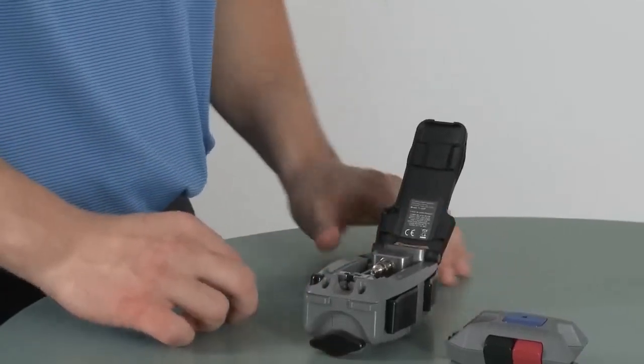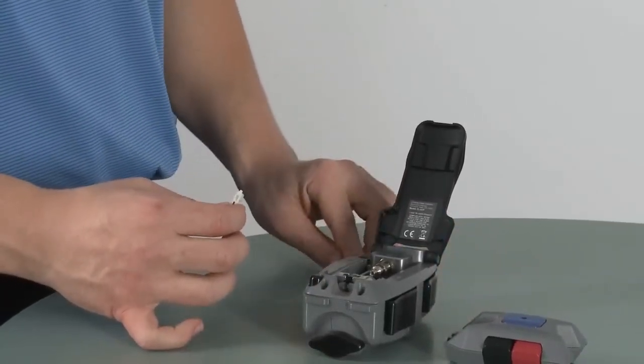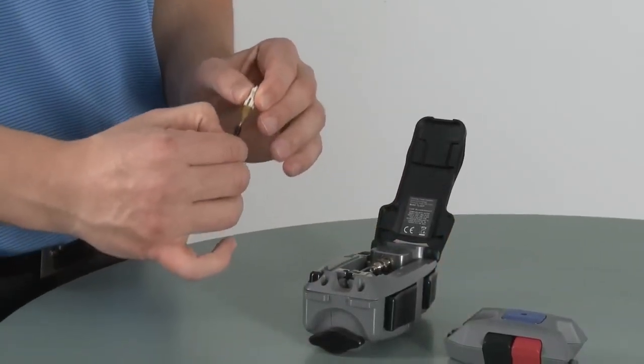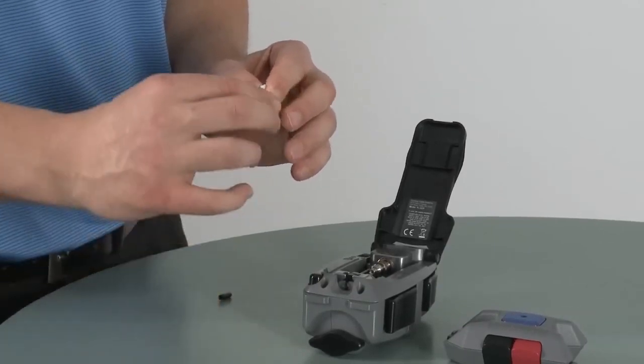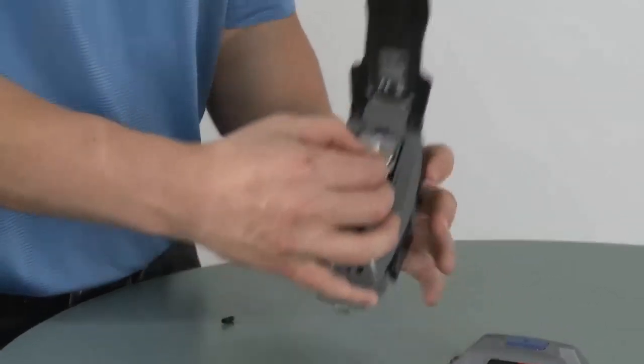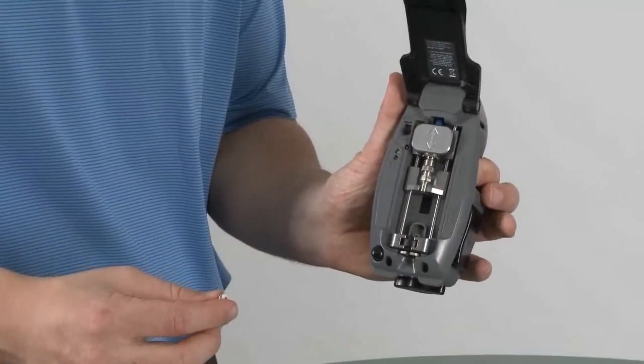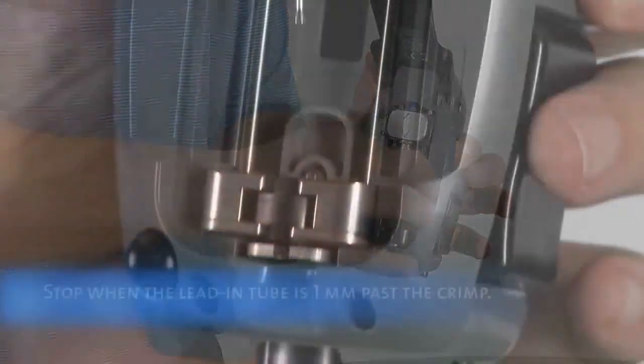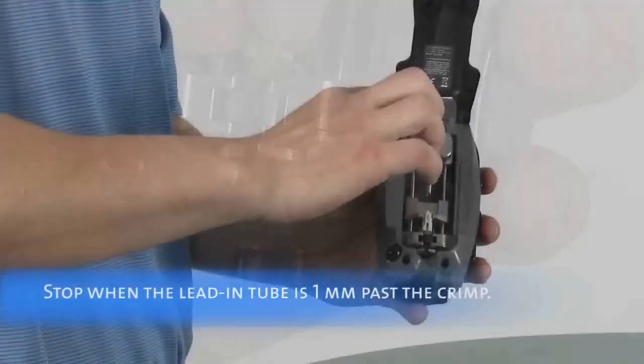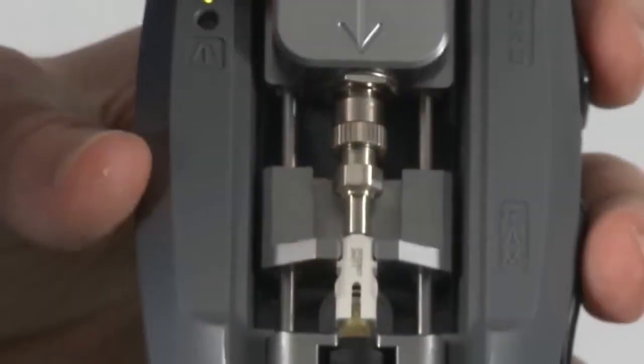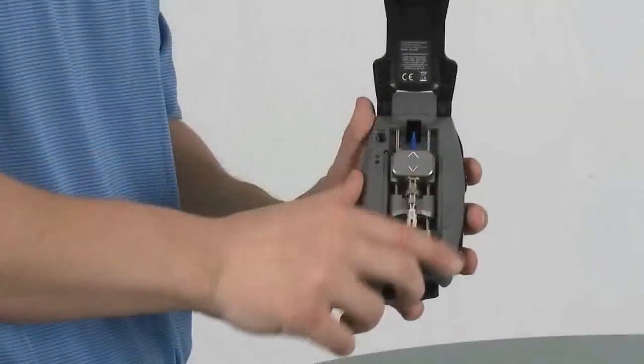Next grab your connector, remove the dust cap, and the plastic shroud protecting the lead-in tube. Grabbing the tool in our left hand, gently press down on the load button and insert your connector. Slide the VFL coupler down so the ferrule adapter is seated in the connector.